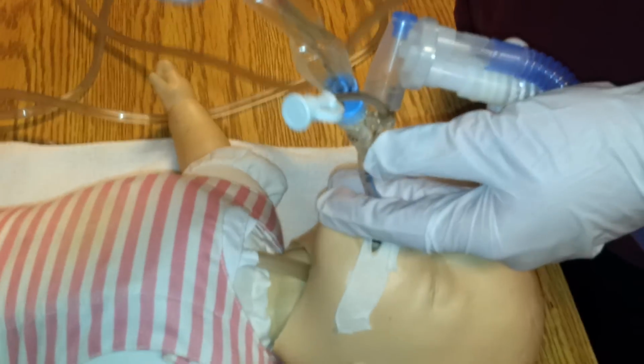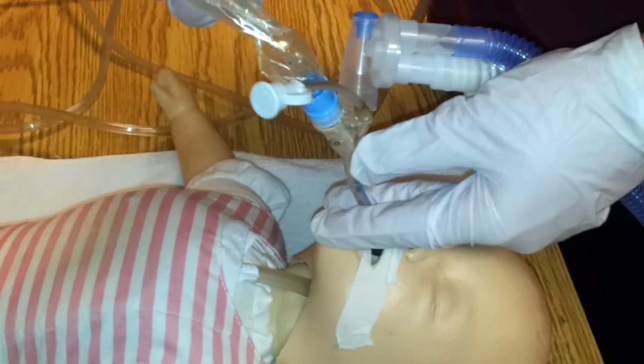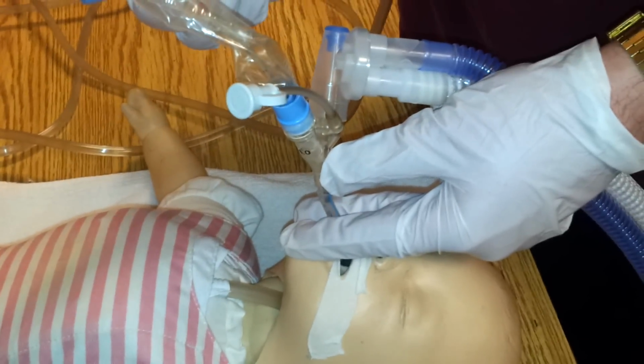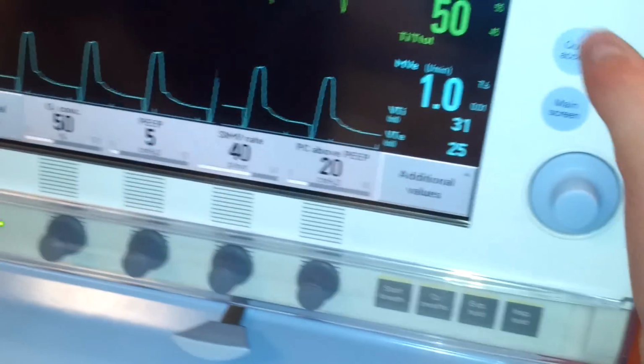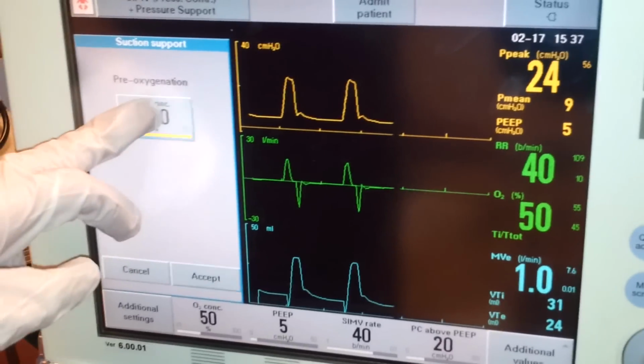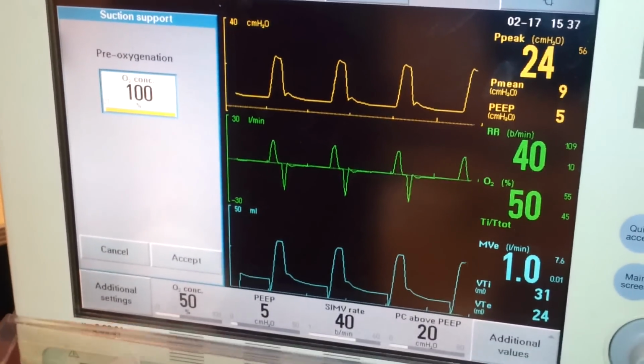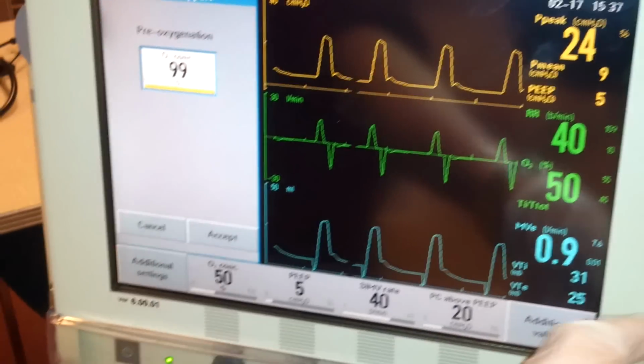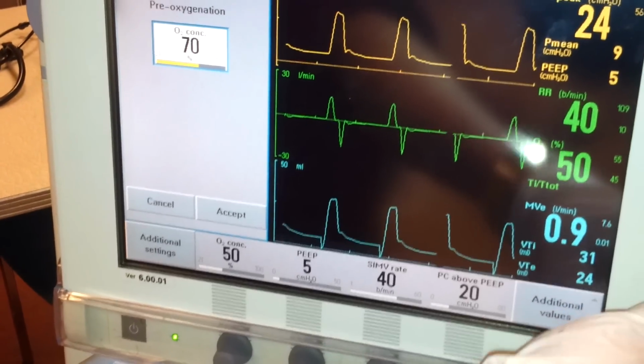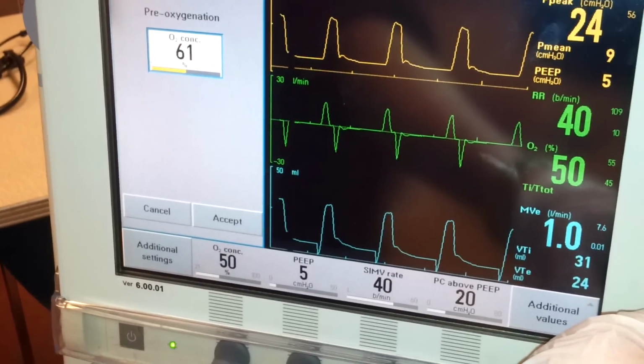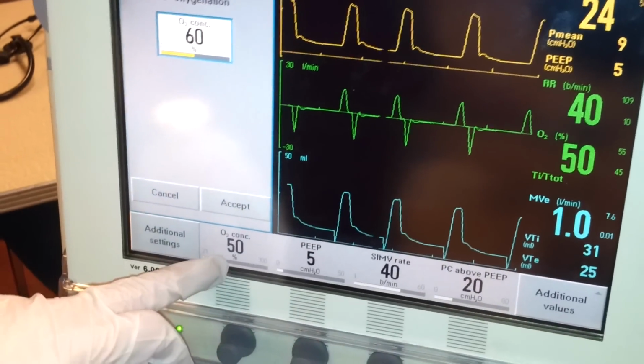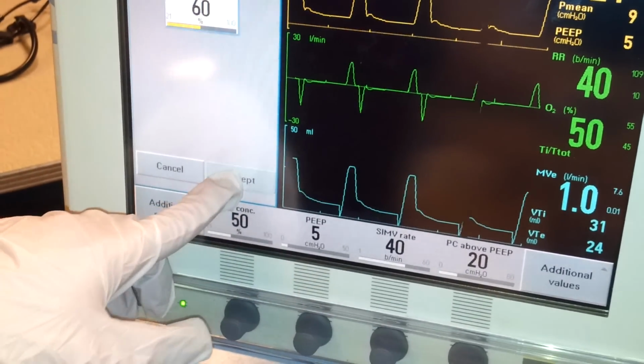So with closed suction, you also want to pre-oxygenate. So you can do that on suction support, the same as open suctioning. So we'll set that the same as we did for open suctioning, which is 10 above. So it was originally 50, we're setting at 60. We'll accept that, and now it gives the pre-oxygenation for us.